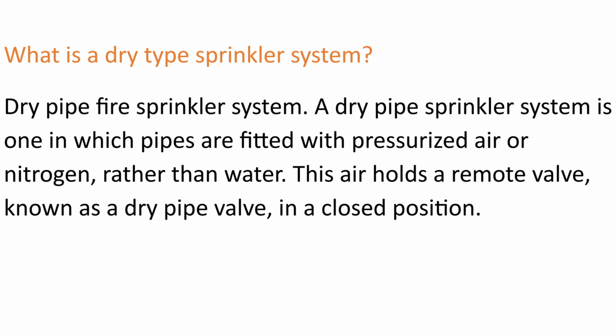What is a dry type sprinkler system? Dry pipe fire sprinkler system. A dry pipe sprinkler system is one in which pipes are filled with pressurized air or nitrogen, rather than water. This air holds a remote valve, known as a dry pipe valve, in a closed position.